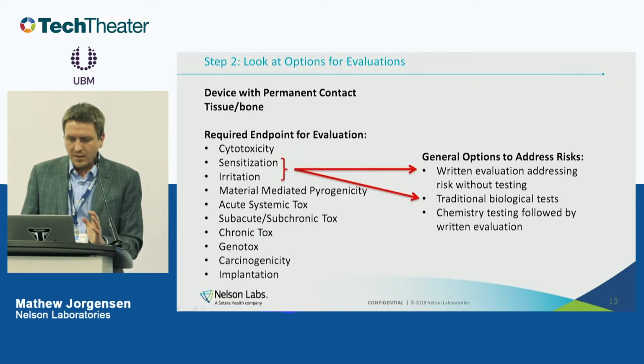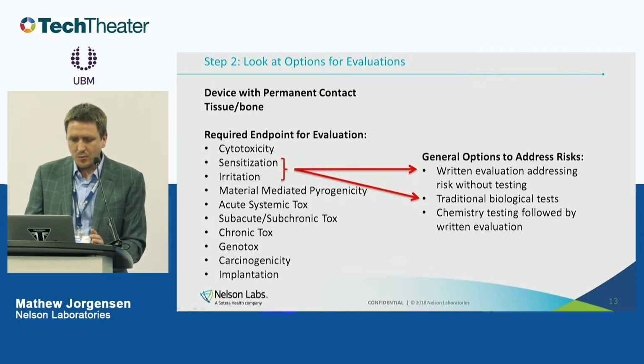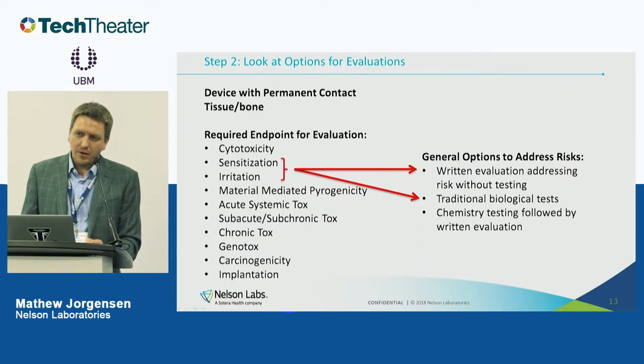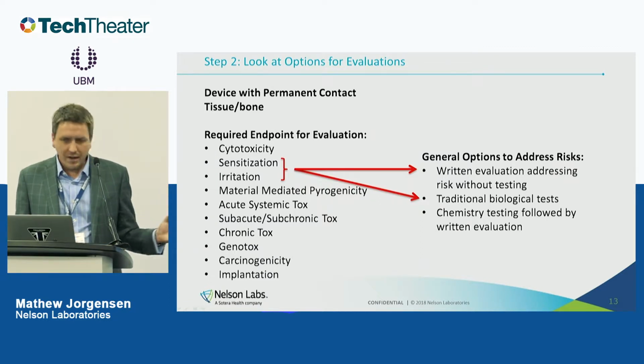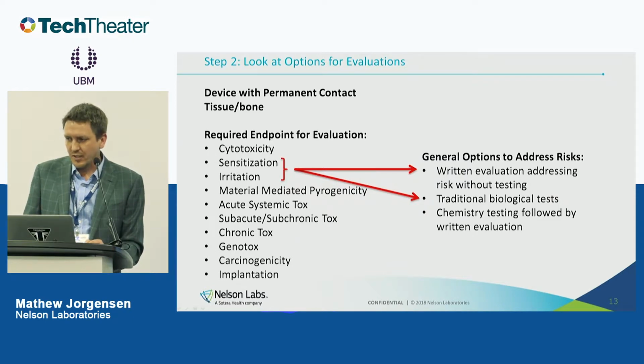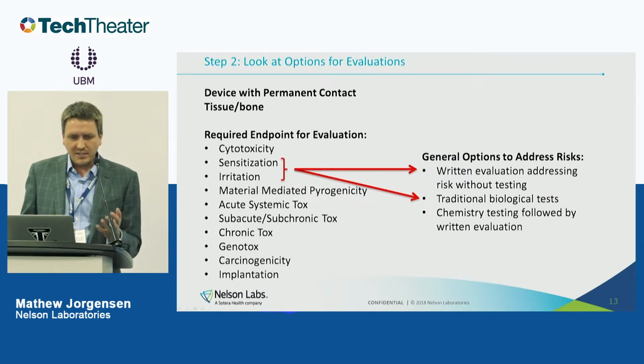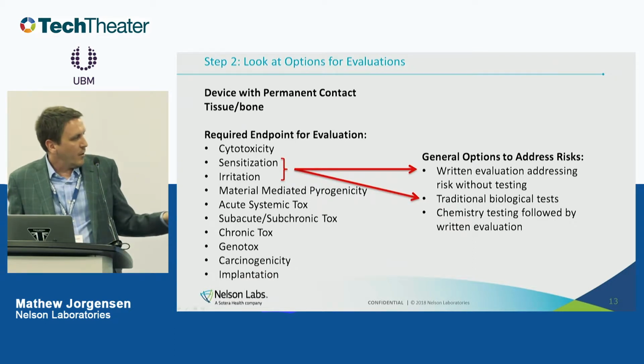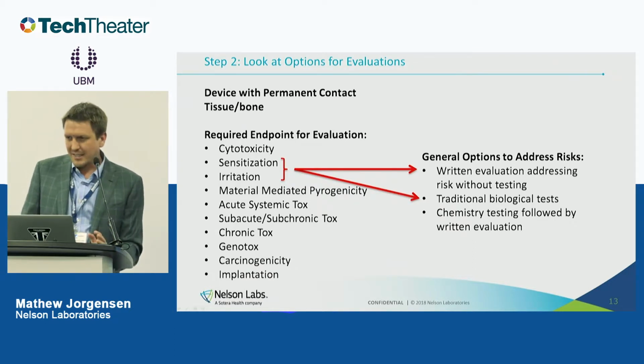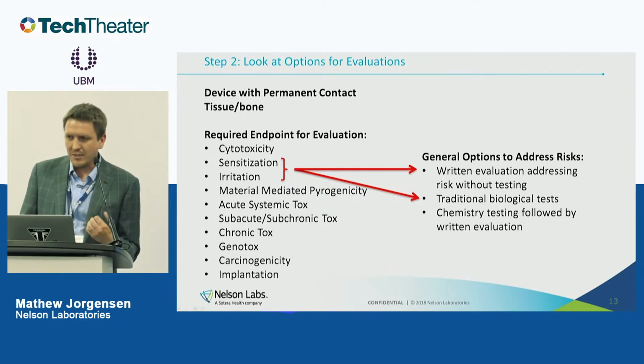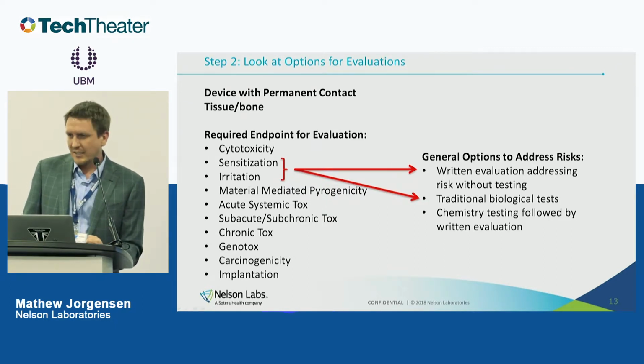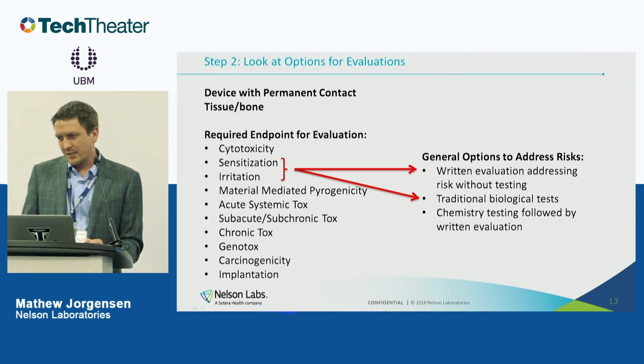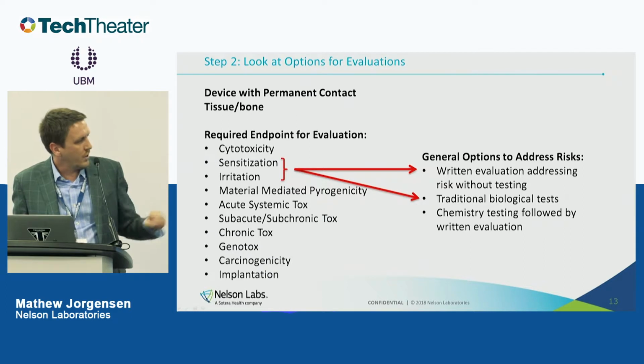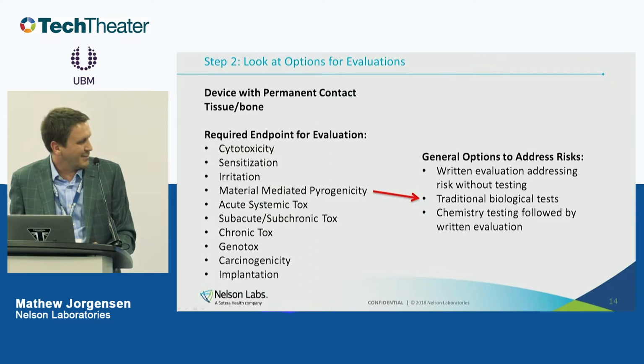The next endpoint, sensitization and irritation: these are ones where you can either do the traditional biocompatibility testing, or you have a shot at doing a written evaluation to address those without doing the testing. There are pluses and minuses to each, but what we have found is that chemistry testing is usually not well accepted by regulators, although as a chemist I feel very strongly that I could support that scientifically. So we would generally only go with a written assessment or traditional testing for that. The material mediated pyrogenicity is one that for now is really best to do just the testing.